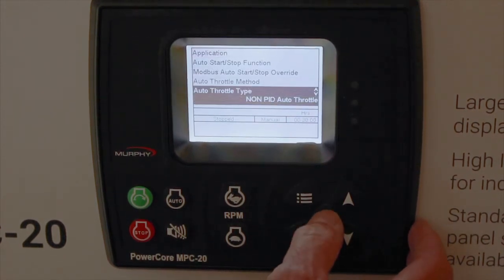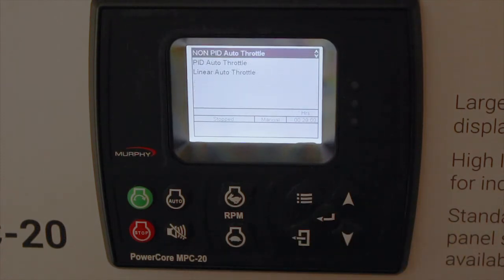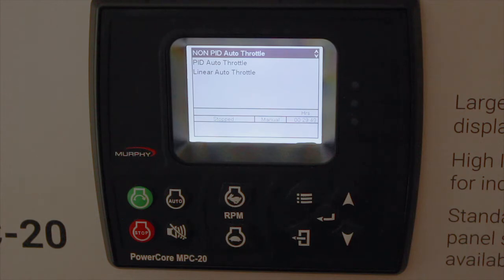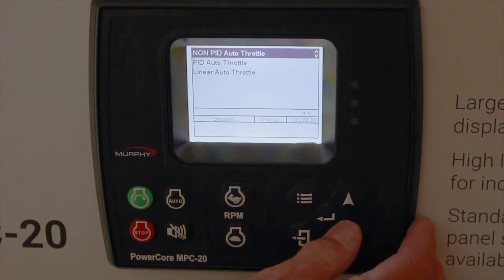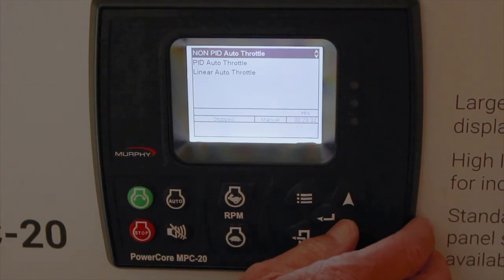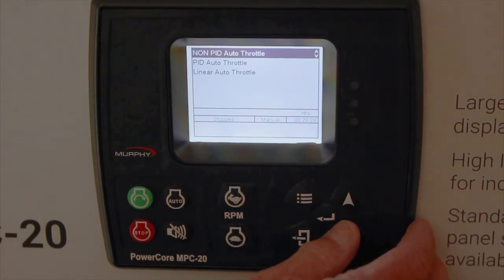Auto throttle type options are non-PID (the default), PID, and linear throttling. Linear throttling is used where there's no set point to maintain, such as with a level — you throttle between the min and max pressure or level proportionally between the two set points. This is useful for smaller sumps where you don't want to chase the level, but want RPM and level to track together.